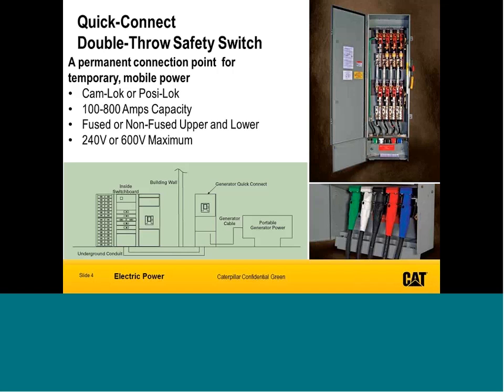This allows for, in a lot of cases, not requiring a licensed electrician to make the connection, whereas connecting to actual bus bars with bare cables many times would. So either your generator rental provider or your facility engineer can make this connection and throw the switch, and you're back up and running in the least amount of time possible.